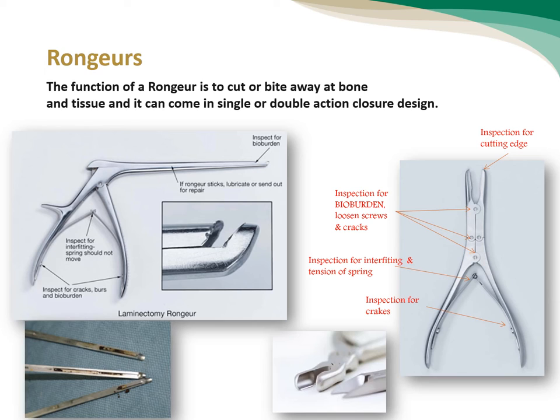We have to check all of the screws, of course, as usual, and any bioburden in between the hinges. We have to check the tip. It's very important to make a test by cutting on a paper or cardboard, a small strong paper, to see the cut edge. Is it okay or not? We see here a laminectomy rongeur with a damaged tip.